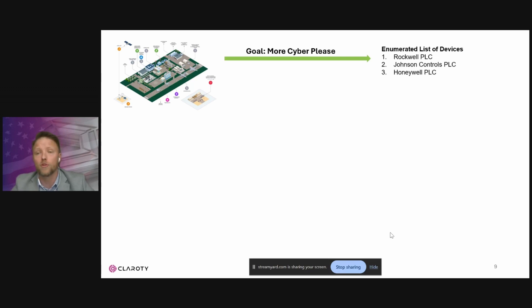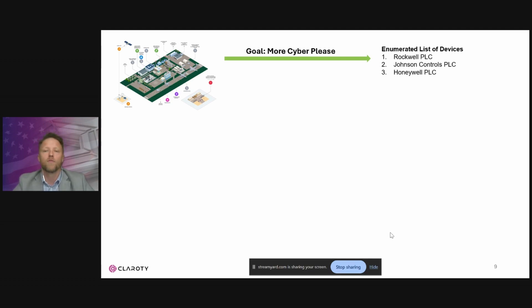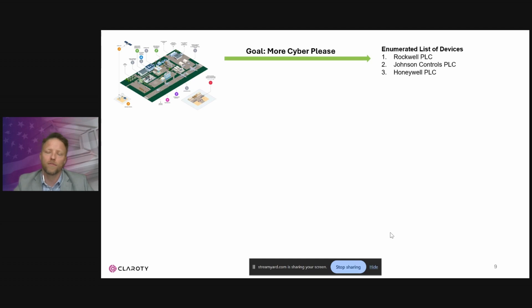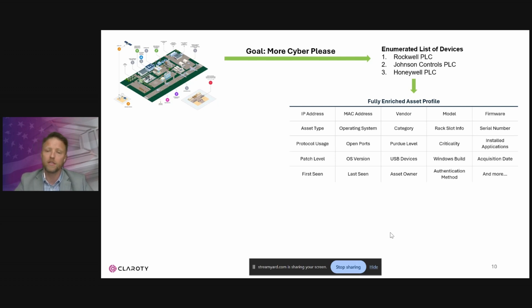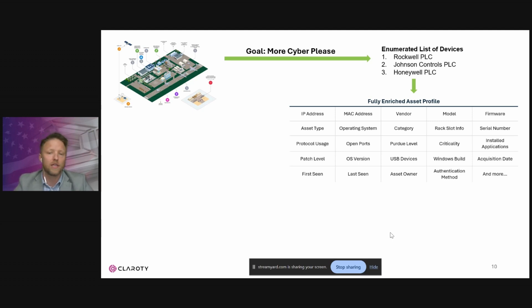Step one is developing an enumerated list of devices. Most of the Department of Defense has been walking around with clipboards and spreadsheets, but they're moving toward automating the process for developing lists of programmable logic controllers — you might have a Rockwell PLC, a Johnson Controls PLC, or a Honeywell PLC, depending on the specific OT environment. You also have to know the vendor, the model, and the firmware, because unless you know the firmware on a specific device, you can't determine if there's a vulnerability against that system.